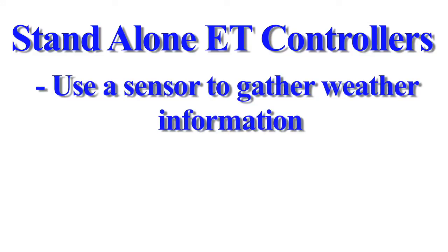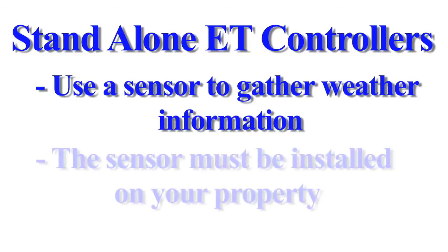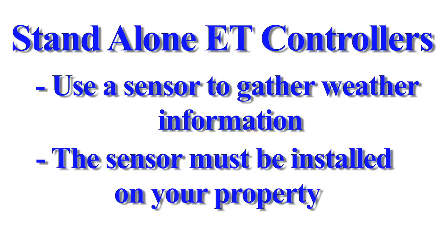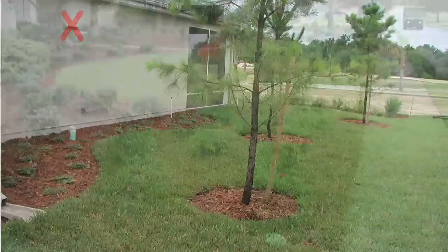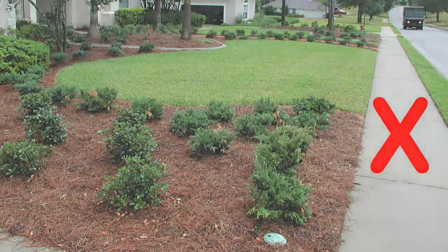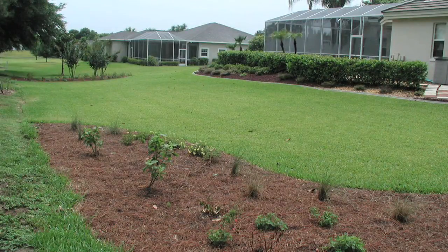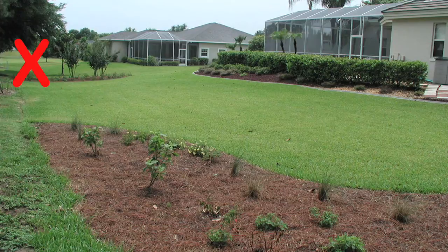Stand-alone ET controllers use on-site sensors to gather weather data and calculate ET. These sensors have to be installed in the landscape or on the side of a house. Where you choose to locate your sensor is important. The sensor must not be obstructed by the roof or placed near outdoor appliances or structures that emit heat, such as air conditioning units, dryer vents, sidewalks, and driveways. For best results, the sensor should be placed in a relatively open area that has adequate airflow and is not obstructed by trees. Improper placement of the sensor could lead to over or inadequate irrigation.